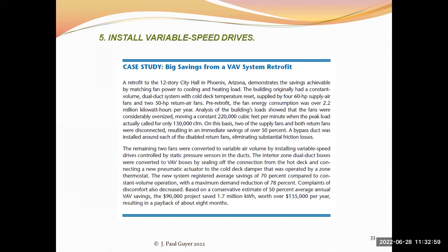And complaints from occupants decreased, and based on a conservative estimate of 50% average annual VAV savings, this $90,000 project saved 1.7 million kilowatt hours of energy, worth over $135,000 a year, resulting in a payback period of only 8 months. So a big, highly cost-effective example.